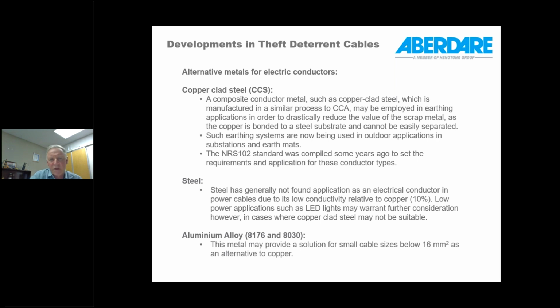It's a similar process to the manufacturing of copper-clad aluminium, and it can generally be applied in earthing applications to reduce the value of the scrap metal, because the copper is bonded to the steel inner core and it cannot really be mechanically separated. So there's quite a number of these applications now which use copper-clad steel in substations and earth mats. The NRS 102 standard was compiled some years ago, and that sets some of the requirements for these conductor types.